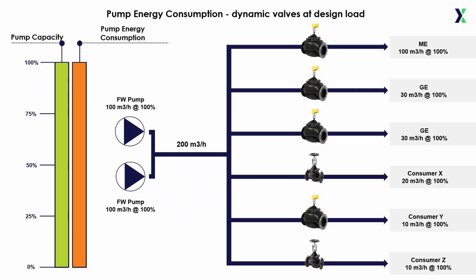But unlike static systems, here we apply dynamic valves. Dynamic valves automatically regulate flow, ensuring that each consumer receives exactly what is needed. No more, no less. The dynamic valves offer advantages such as flexibility. One pipe loop can be closed without influencing other parts of the system. Also, the commissioning process is simplified. However, when the system runs at full capacity, the pumps are running at an energy consumption also at 100%.